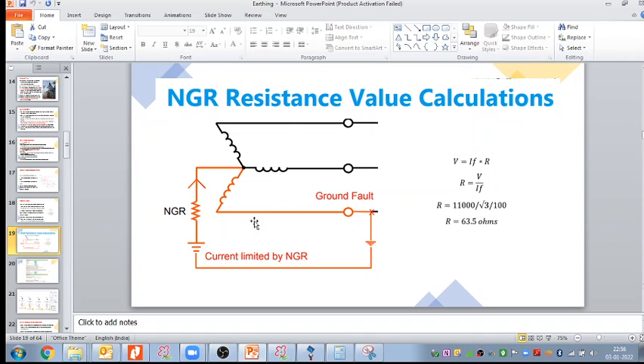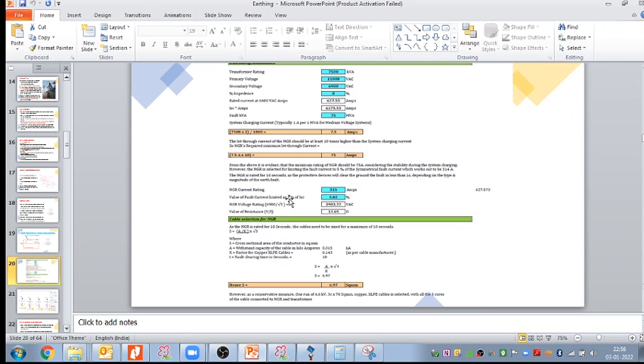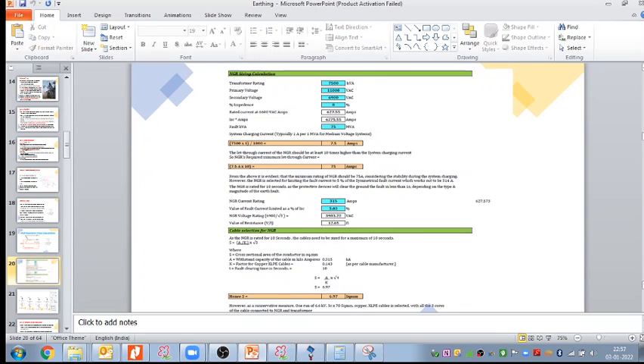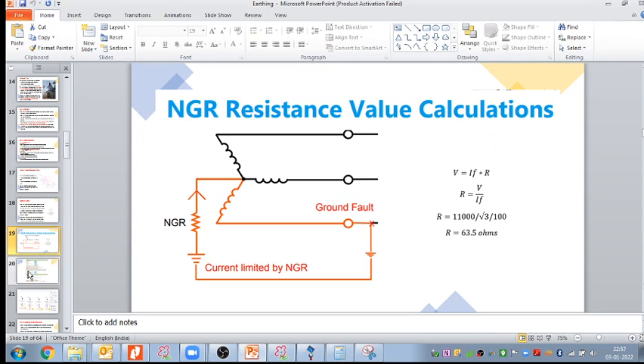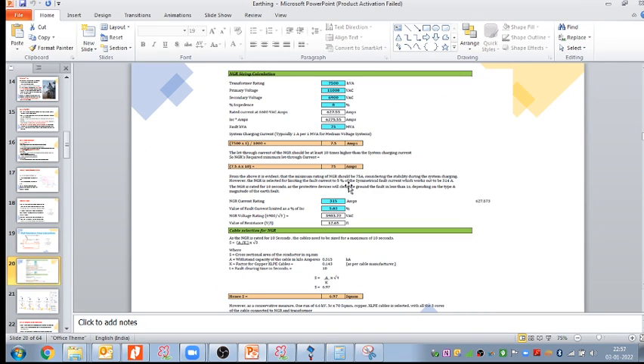The same we have taken here, this star winding, where a ground fault happens. Here we put the NGR in the return path of the ground, and this NGR value of 63.5 ohm we can put here. This is one calculation that we do for any project submission. This is the thumb rule, the format of the calculation that we have to do. NGR sizing calculations, these are the steps that we perform. Okay, and I'll come later on to this.